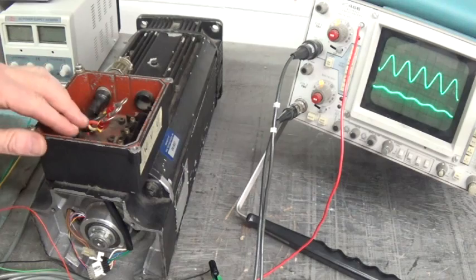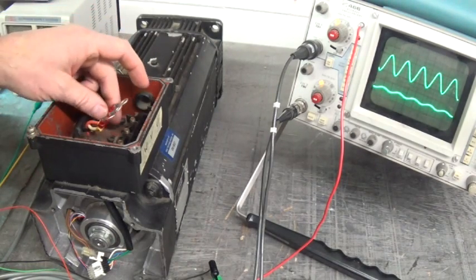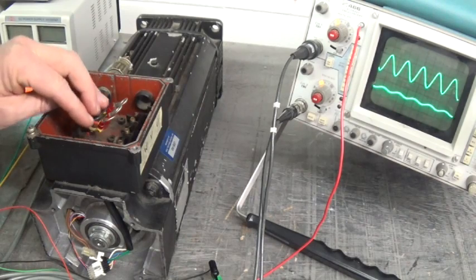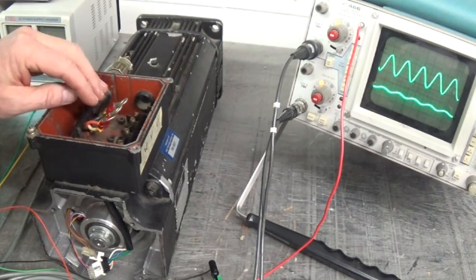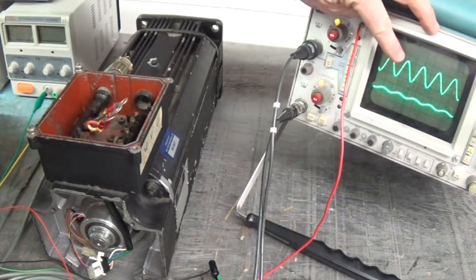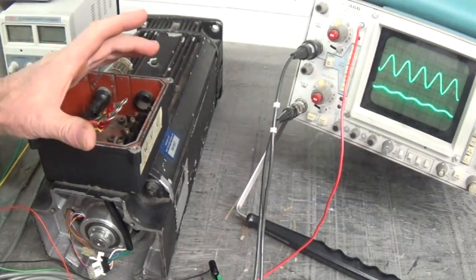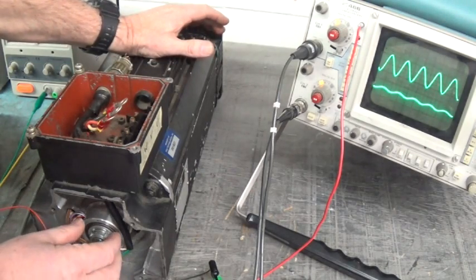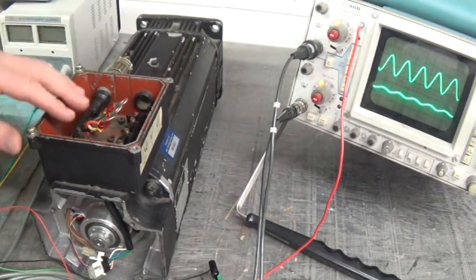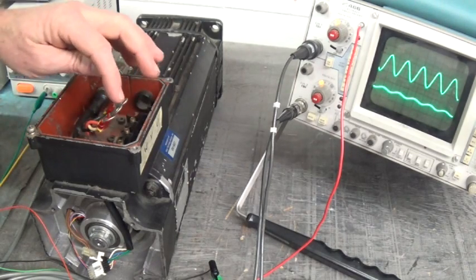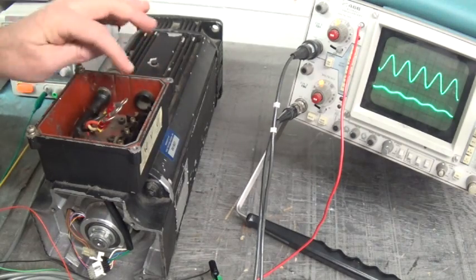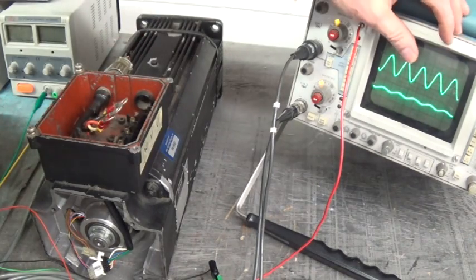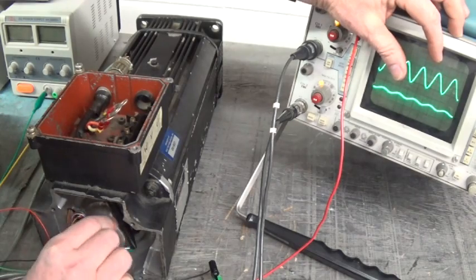And we'll write down who we made positive and who we set at ground on the windings of the motor—U, V, and W—who made that condition. And when the motor's reassembled and we put that resolver back on there, we'll lock the rotor by putting positive five volts here and ground there or wherever, and we'll rotate the resolver until we have that condition duplicated.